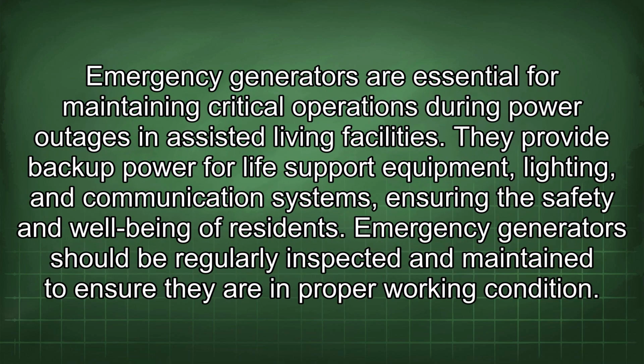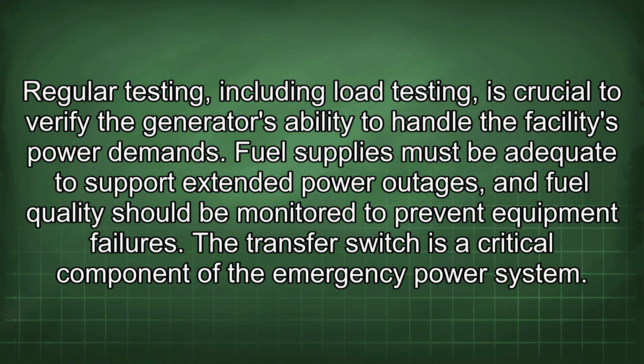Emergency generators are essential for maintaining critical operations during power outages in assisted living facilities. They provide backup power for life support equipment, lighting, and communication systems, ensuring the safety and well-being of residents. Emergency generators should be regularly inspected and maintained to ensure they are in proper working condition. Regular testing, including load testing, is crucial to verify the generator's ability to handle the facility's power demands. Fuel supplies must be adequate to support extended power outages, and fuel quality should be monitored to prevent equipment failures.